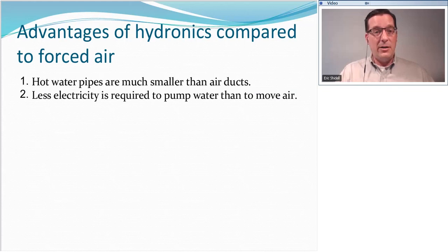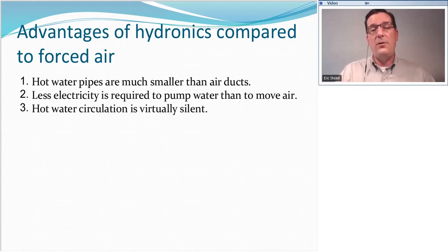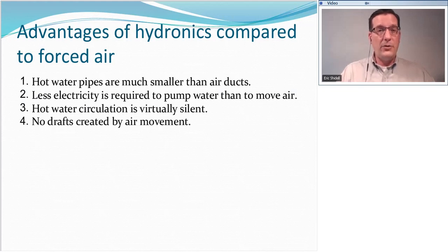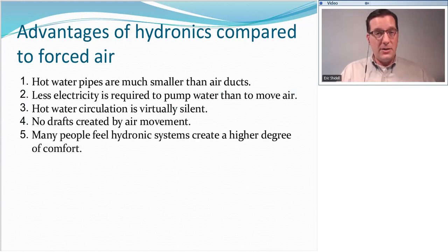Because of what I just said earlier, less electricity is required to pump water than to move the equivalent amount of air. There's an advantage there as well. Another advantage: hot water circulation is virtually silent. So people who don't like to hear the sound of that fan or don't like to hear air circulation, there's an advantage there. We don't have drafts associated with air movements in a hydronic system. And this is subjective, of course, but a lot of people feel that hydronic systems deliver a higher degree of comfort.